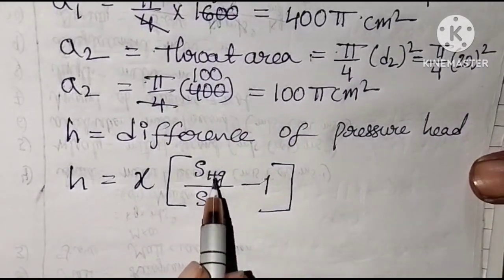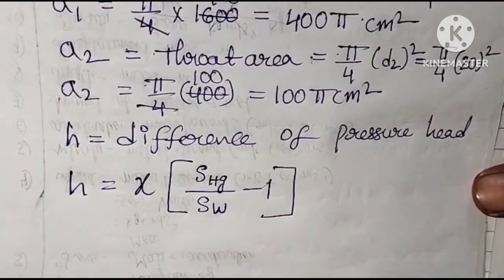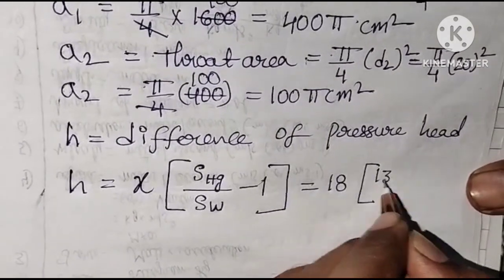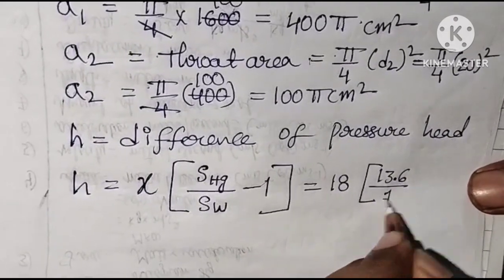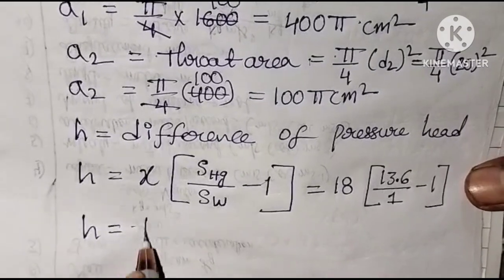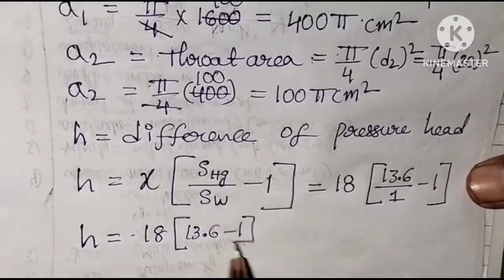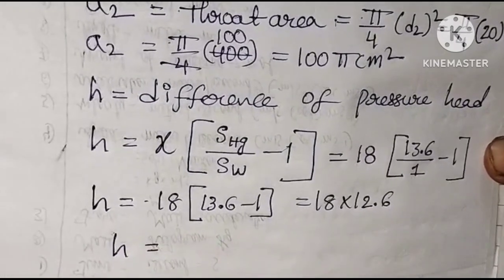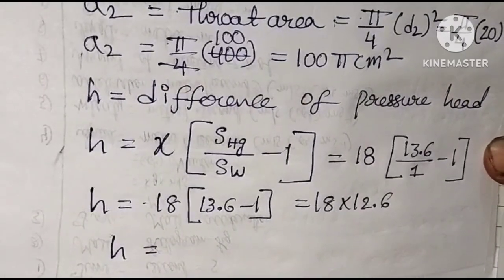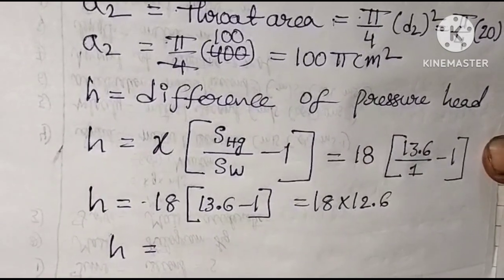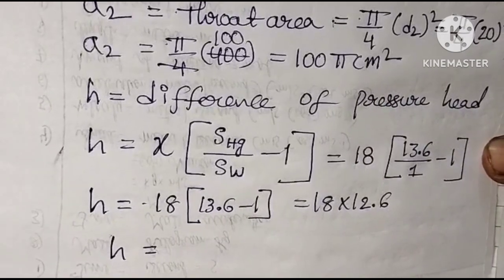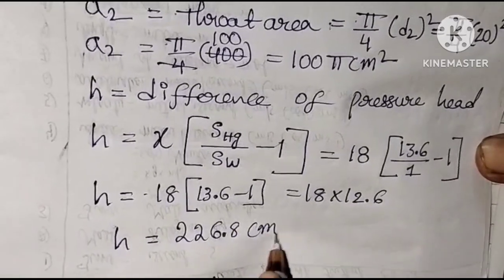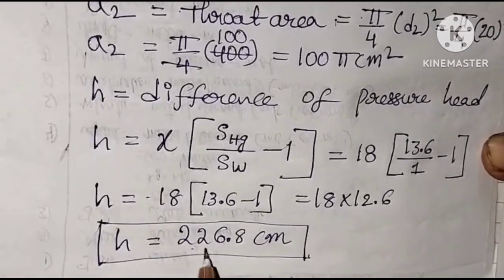Since we are using a heavier liquid than the working fluid, H = X × (S_Hg / S_W − 1). With X = 18 cm, specific gravity of mercury = 13.6, and specific gravity of water = 1: H = 18 × (13.6 − 1) = 18 × 12.6 = 226.8 cm. So the difference of pressure head is 226.8 cm.